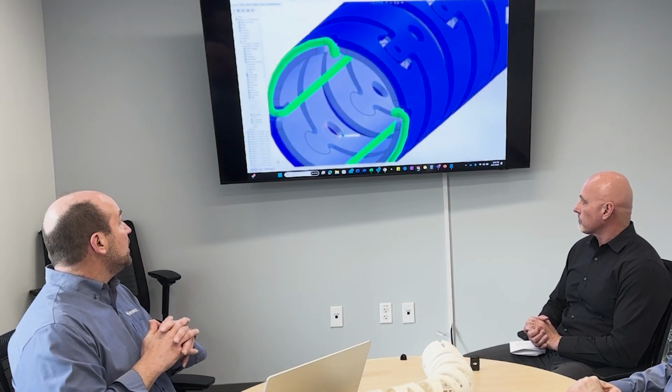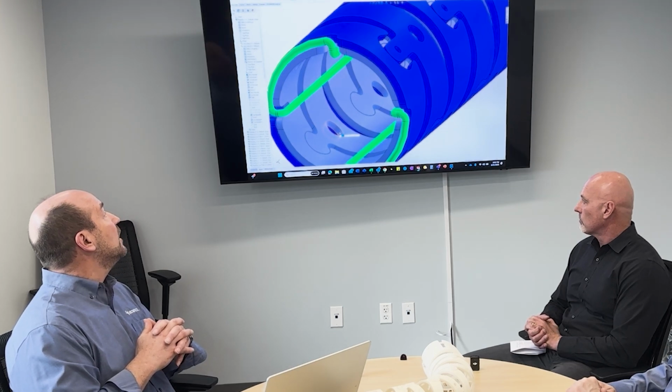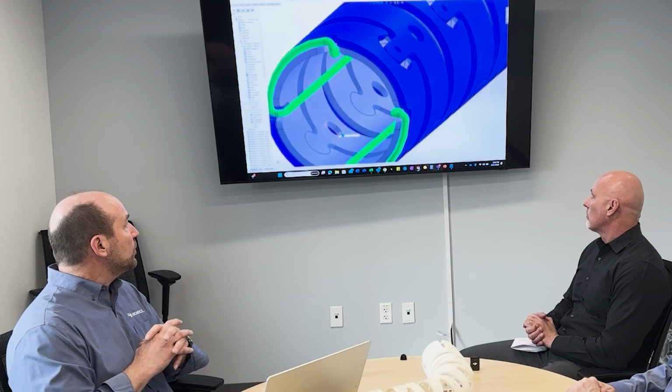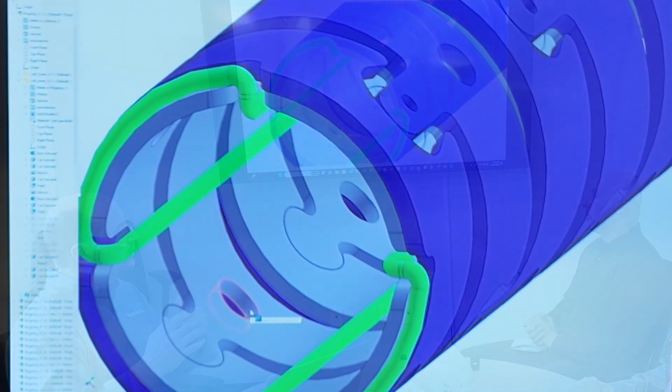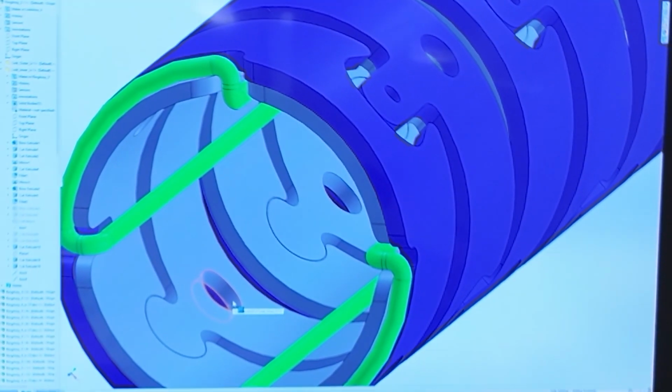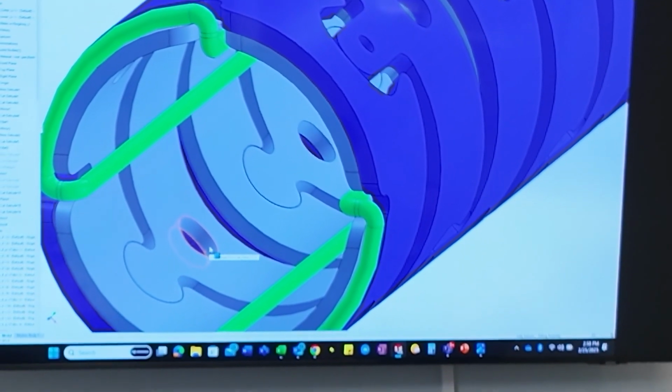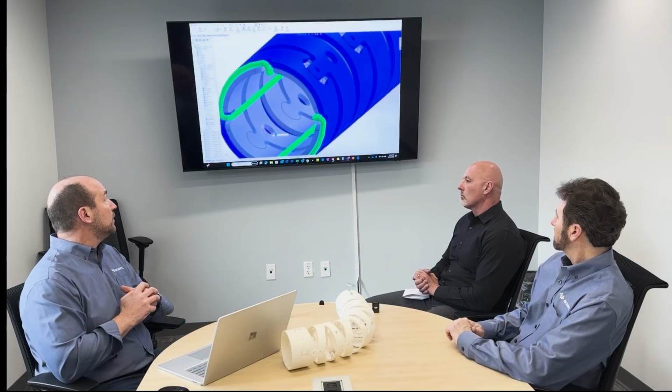We can make the end sections just slightly different so that they can attach to either the proximal or the distal end of the mating component. Interesting. So what you see is the holes in there on both the inner and outer rings. We put locating pins through, and we can weld the whole link assembly up with one fixture, tooling all of them together, and then programming the welder to weld each one of those individually.